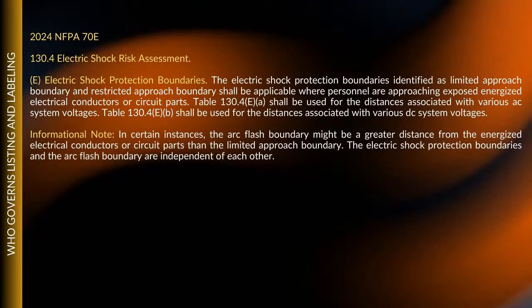That's going to take me back to one more spot here that I want to point out. This is why I like to point this stuff out so everybody understands exactly what the intent is when you're looking at 70E. So if I go in and look one more time at 130.5C and get into the estimate of likelihood, it says when you're performing infrared thermography and other non-contact inspections, listen to this, outside the restricted approach boundary.